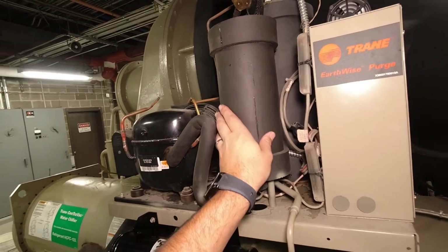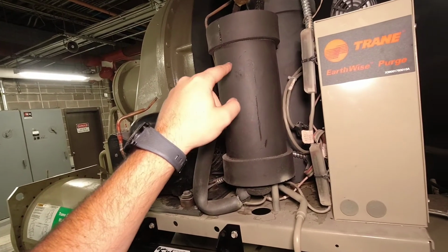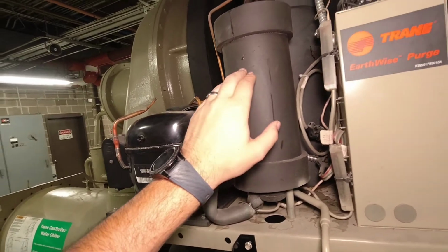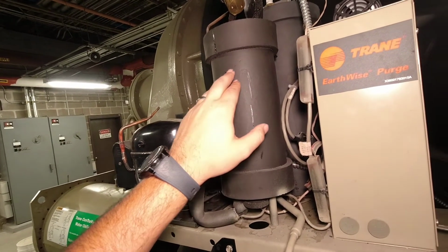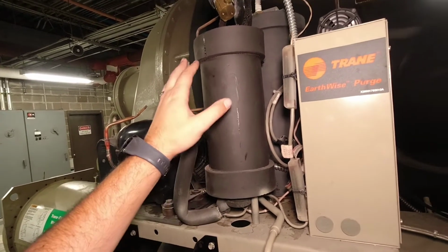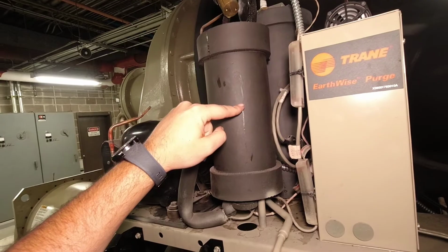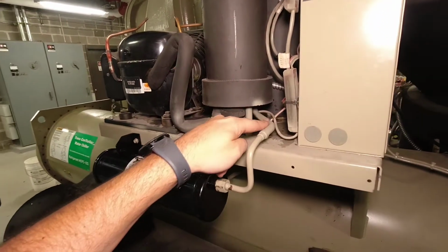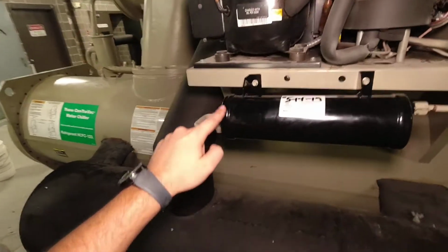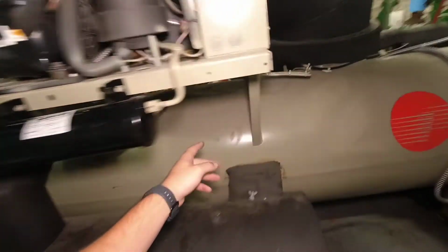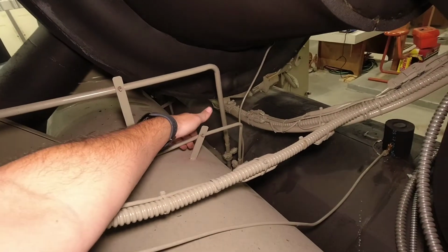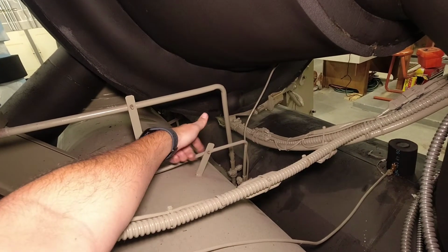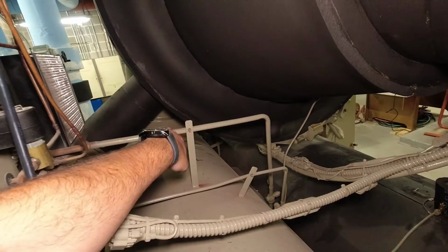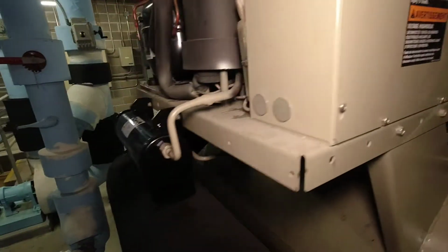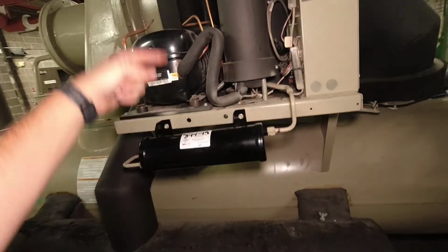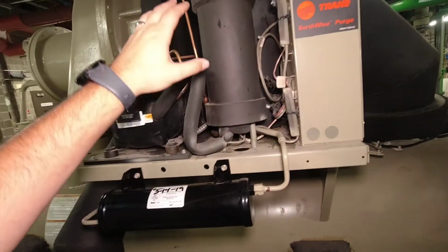And as that compressor cools that coil, the refrigerant condenses at a higher temperature than atmosphere does, or moisture or anything else in the system. So the refrigerant condenses and then comes down out of the tank, and gravity feeds back through this filter and drains back into the bottom of the condenser. And because this is a gravity feed back out, it naturally pulls a siphon and pulls more refrigerant gas back into the tank. So it's just a natural siphoning effect. And that's all it is.